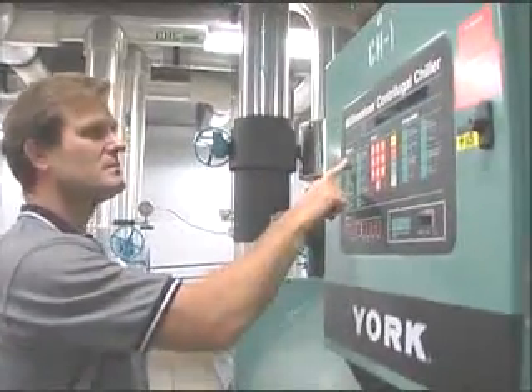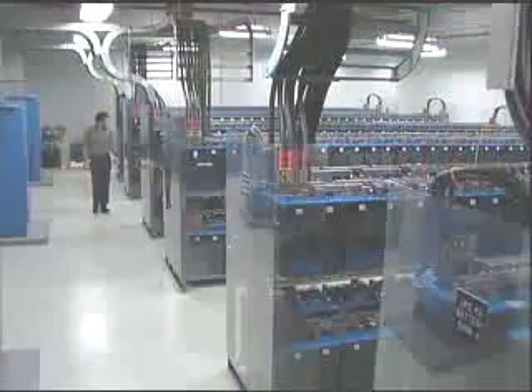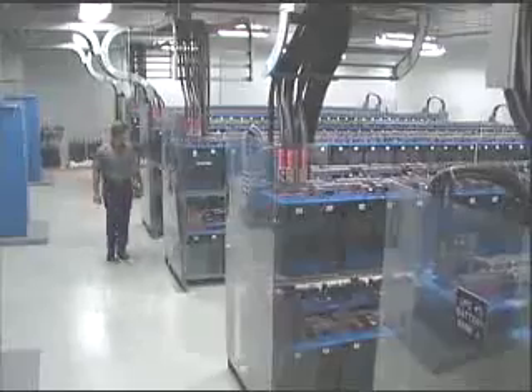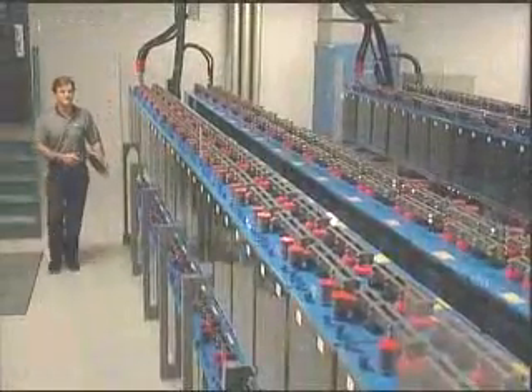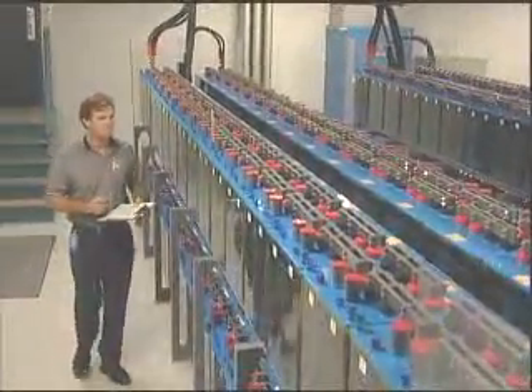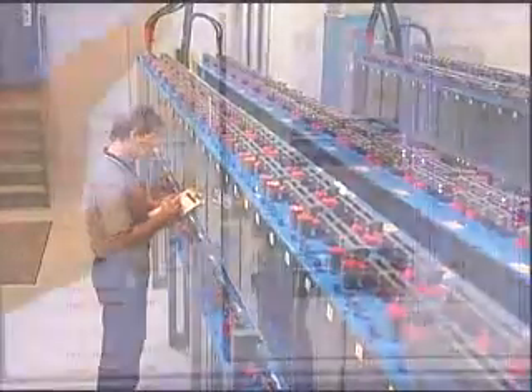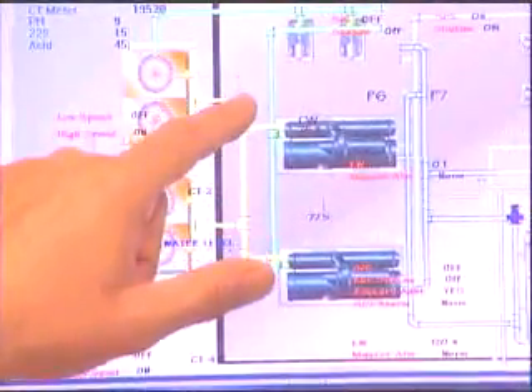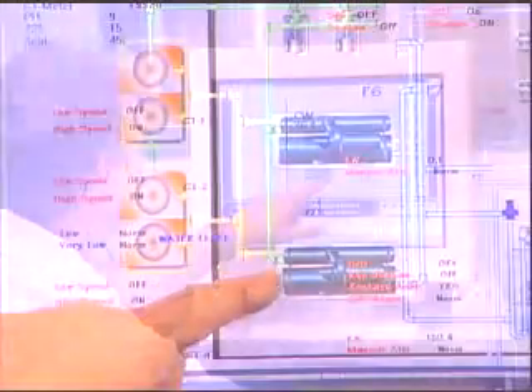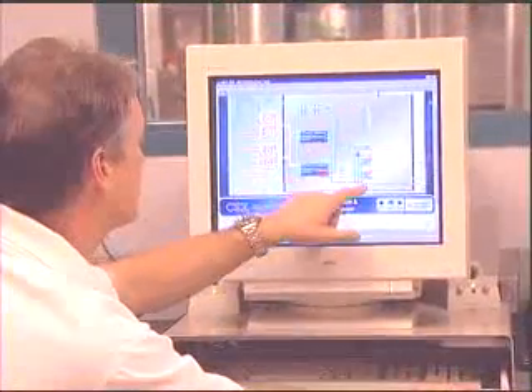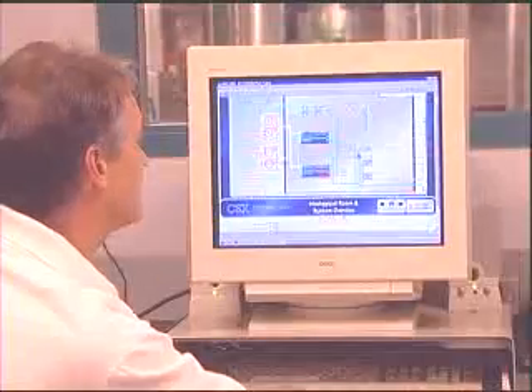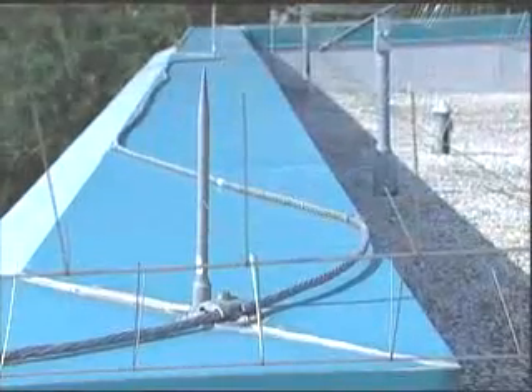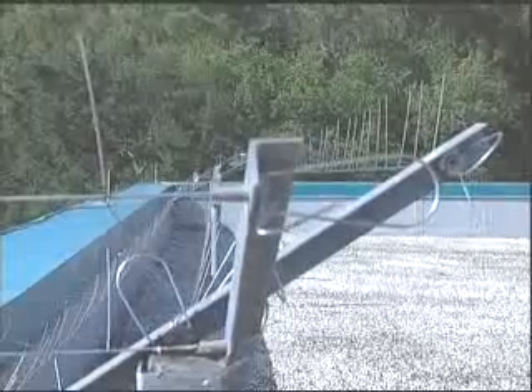Let me put some of this in perspective. The capacity of the UPS battery bank can start 1,800 cars simultaneously, or provide the total power requirements for 60 houses for approximately 30 days. The cooling capacity of our chiller units could provide the cooling requirements for about 320 houses. There are 2 cooling water piping systems that deliver cooling to our heat loads. The lightning protection system consists of a point collection system as well as a dispersion array system.